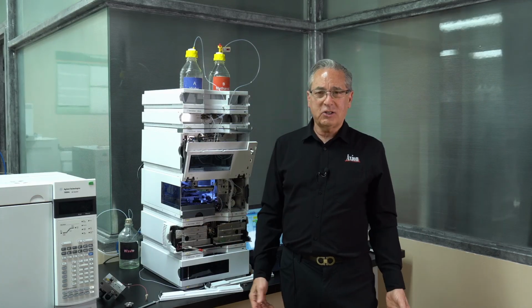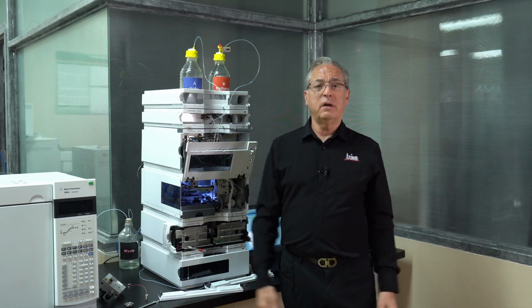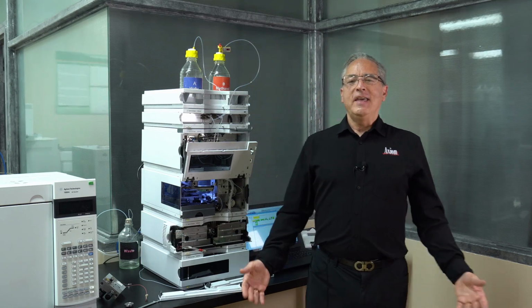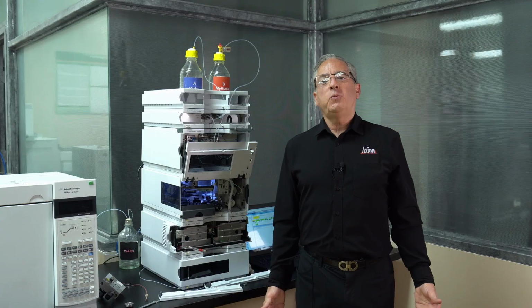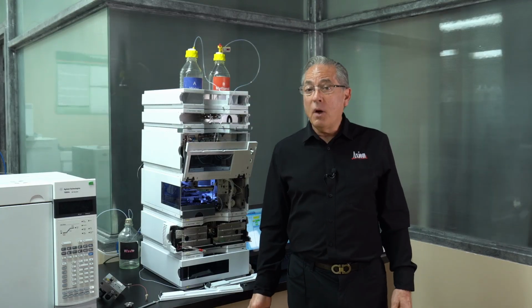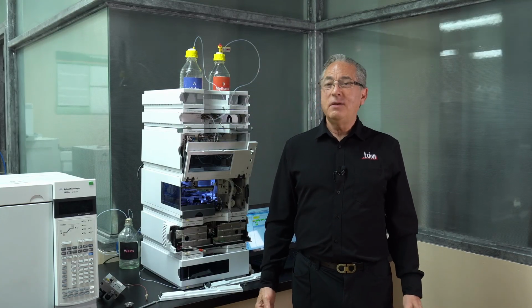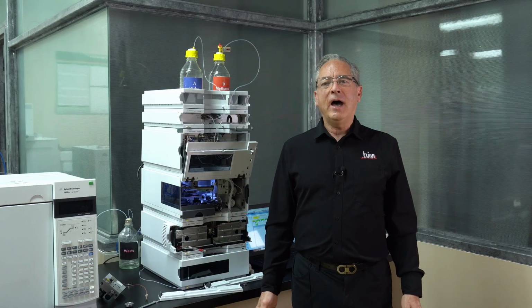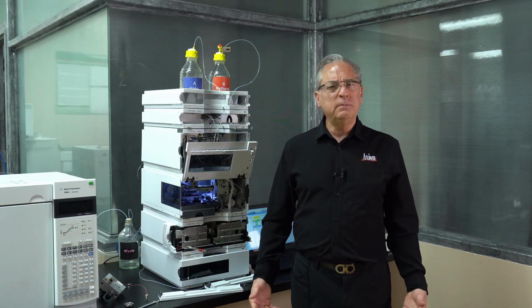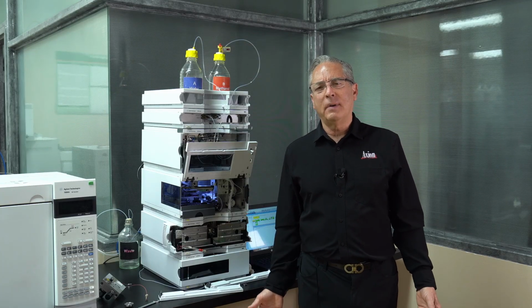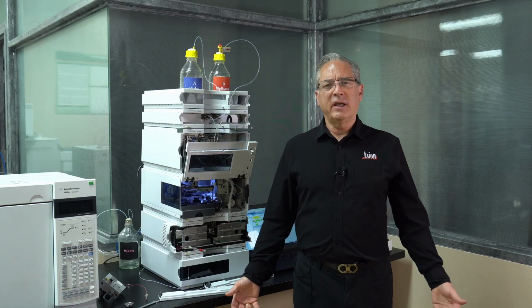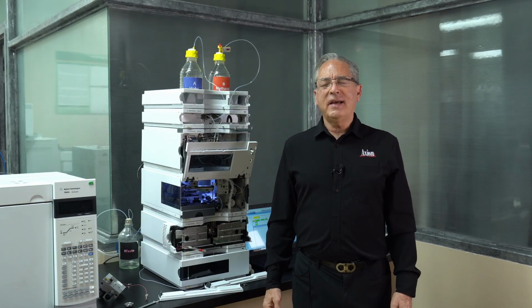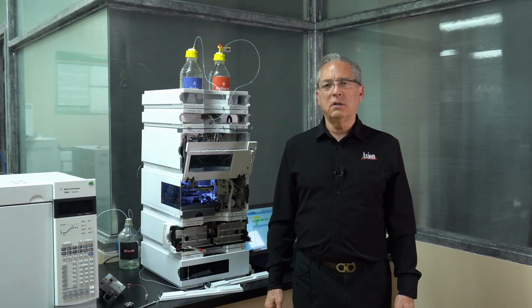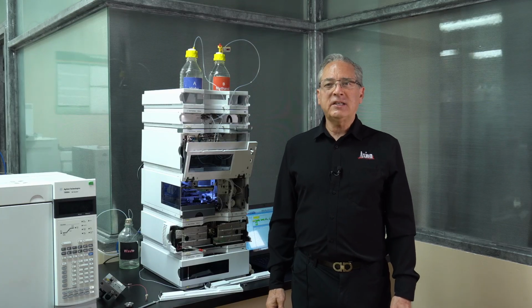And the detector, I sort of joke, the light bulb burns out once a year and you replace the light bulb. You can get a little more sophisticated than that. We can actually monitor the health of the light bulb. We can monitor the energy of it, and we can tell when it's about to go bad. We can do that in the software. But short of that, when the lamp goes bad, we simply replace it. Now, when your lamp goes bad, it doesn't burn out like a traditional filament lamp. It just gets harder to light.